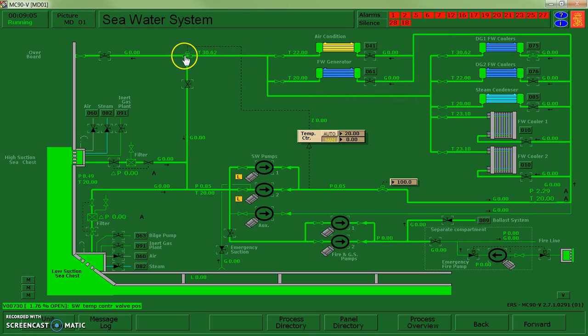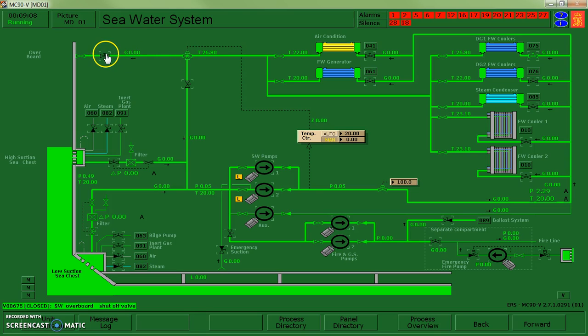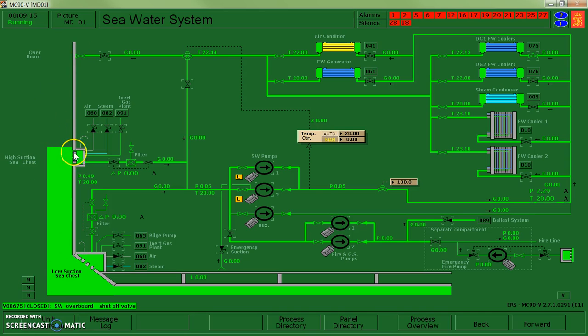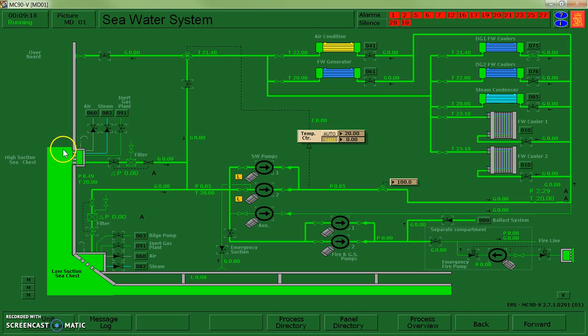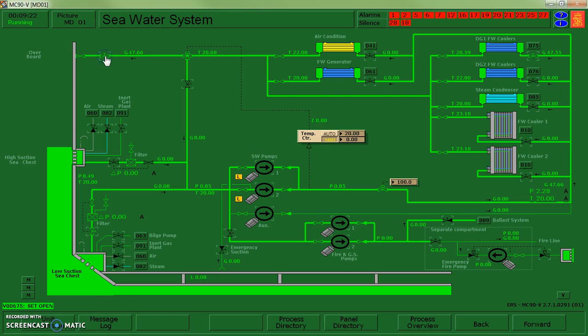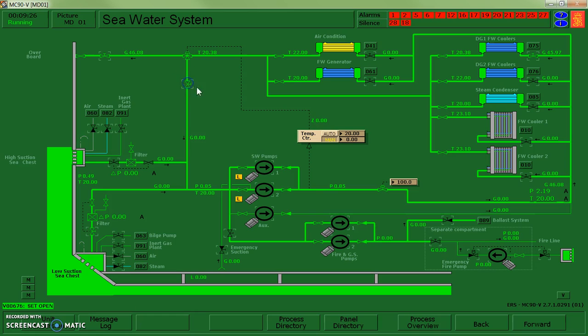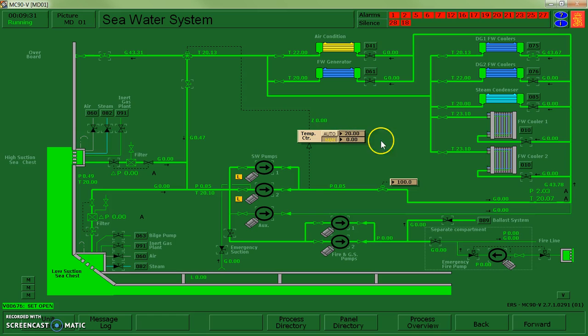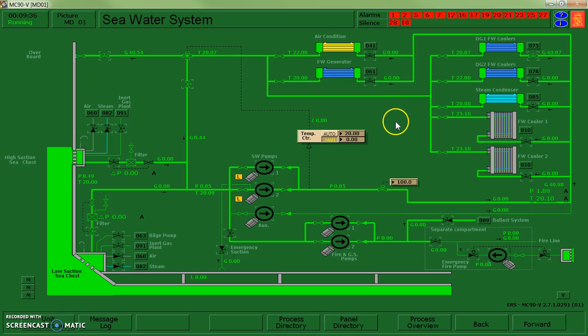And that's going to continue through. Now, a lot of mistakes that get made is that I forget to open up a discharge, so overboard. And really what happens is it just creates a circulation loop. A reservoir it dumps into is a sea or ocean. So it's essentially an unlimited reservoir. But I want to make sure that I have that pathway created. This pathway as well exists, which is a recirculation loop. So it can allow me to change the temperature of cooling water that passes through in case it's too cold or too hot.